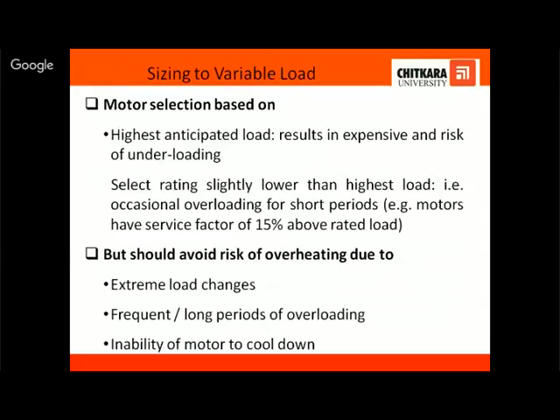Now again, this recommendation should not be given if there is a risk of overheating. Say there are extreme load changes. The motor will not have enough time to cool down. If the motor is not cooling down enough and you have chosen an undersized motor, it may result in overheating, and that will affect the performance of the motor. Otherwise, if the process is such that the overload is momentary, then choose the motor with a low rating and let the motor be overloaded for a small duration.